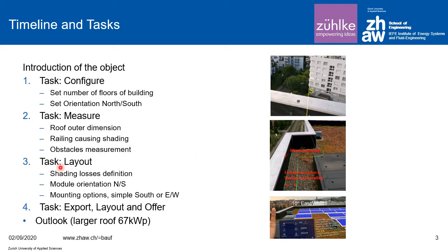Third, the layout is done by choosing the orientation and finding the type of mounting structure — east, west, or south — and also selecting the amount of shading losses that will be allowed. Then the PV modules are displayed on the roof and the optimum planning is chosen.